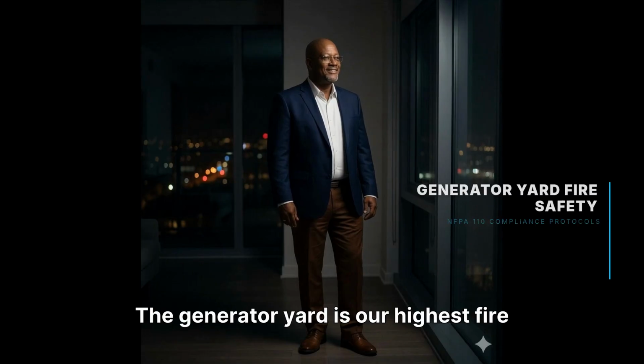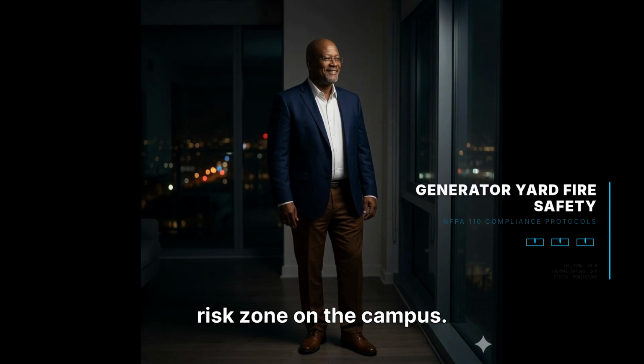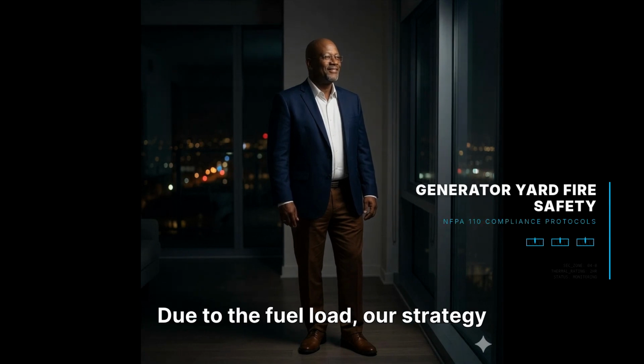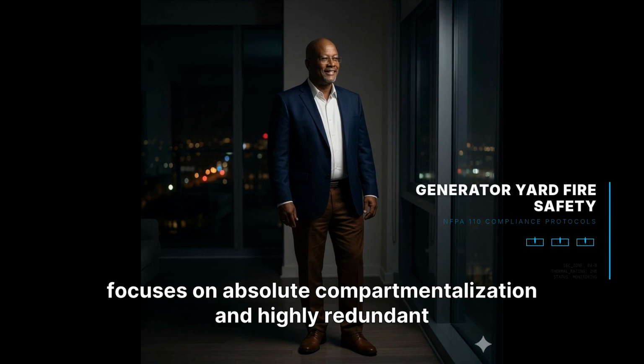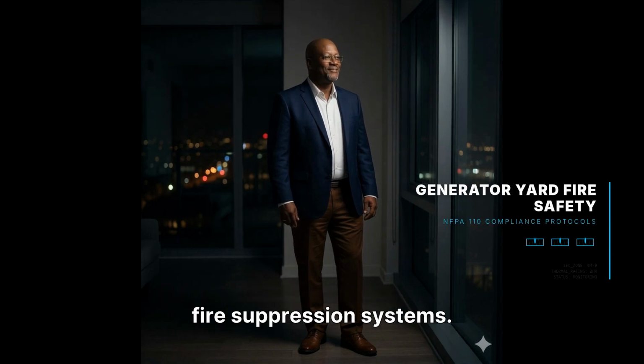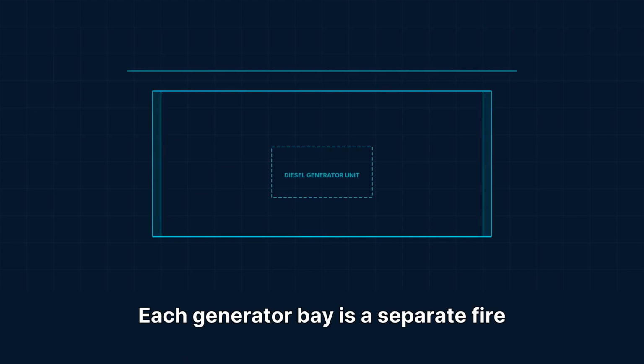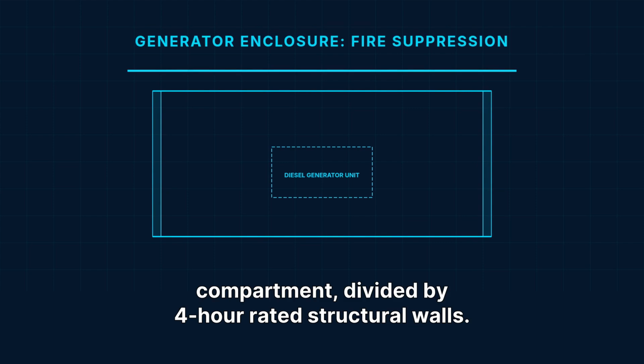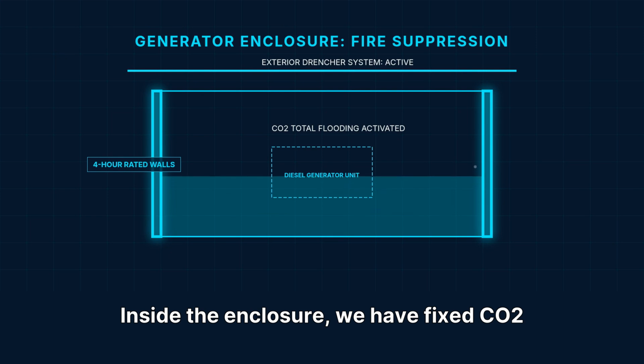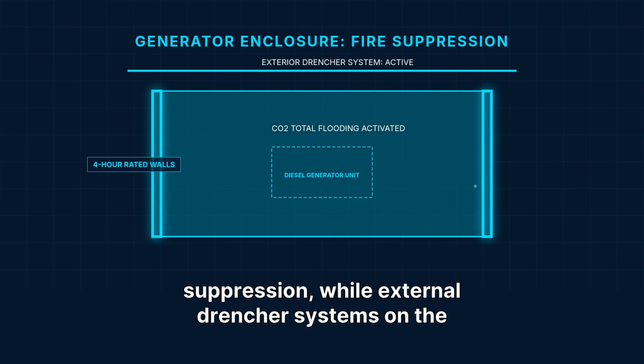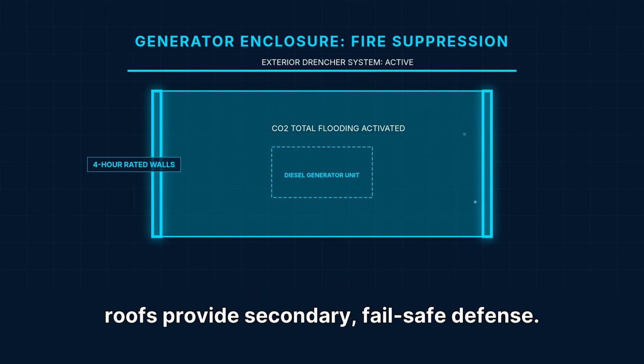The generator yard is our highest fire risk zone on the campus. Due to the fuel load, our strategy focuses on absolute compartmentalization and highly redundant fire suppression systems. Each generator bay is a separate fire compartment, divided by 4-hour rated structural walls. Inside the enclosure, we have fixed CO2 suppression, while external drencher systems on the roofs provide secondary, fail-safe defense.